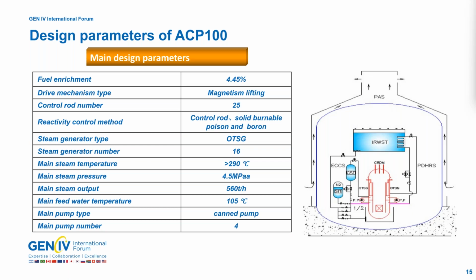The main steam temperature is more than 290. The main steam pressure is 4.5 megapascal. Main steam output is 560 tons per hour. The main feed water temperature is 105. The main pump type is canned pump, and there are 4 canned pumps connected with the reactor vessel. Next, please.